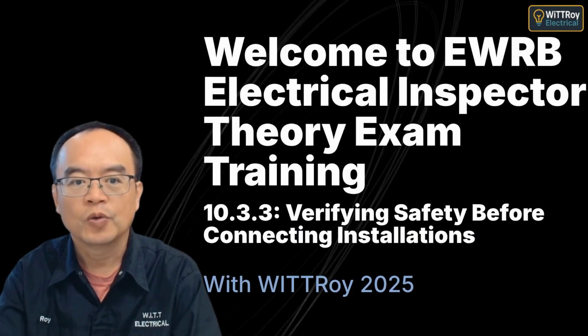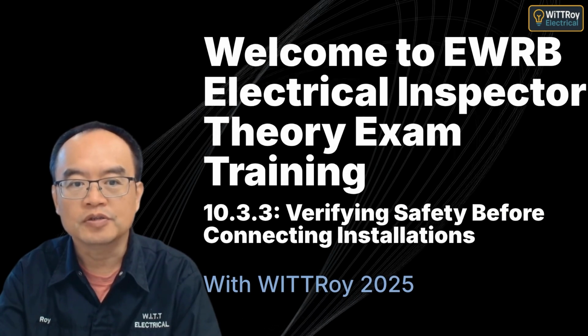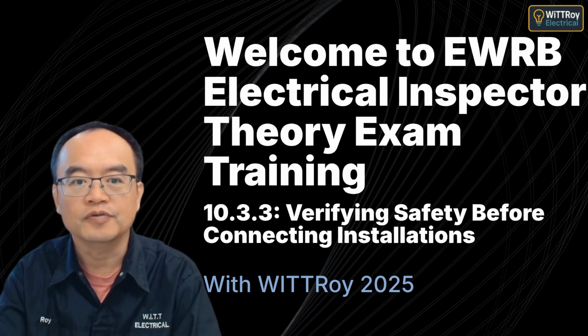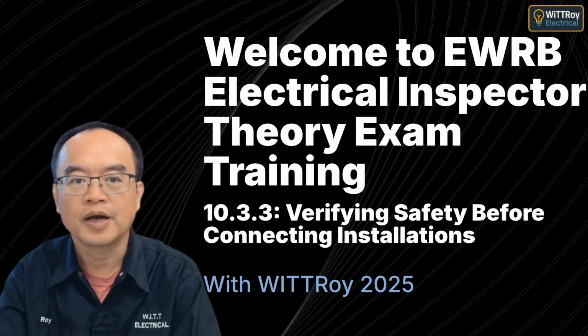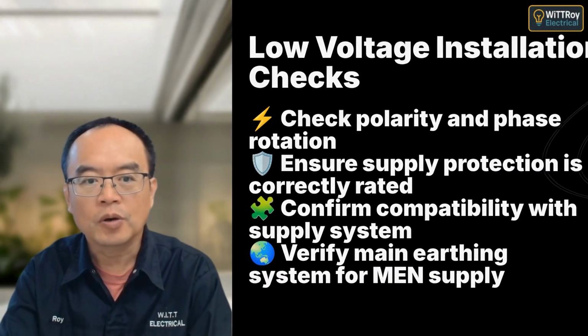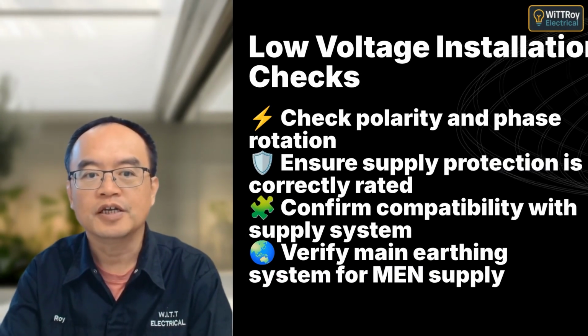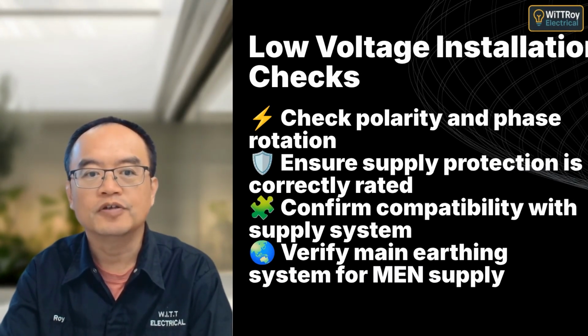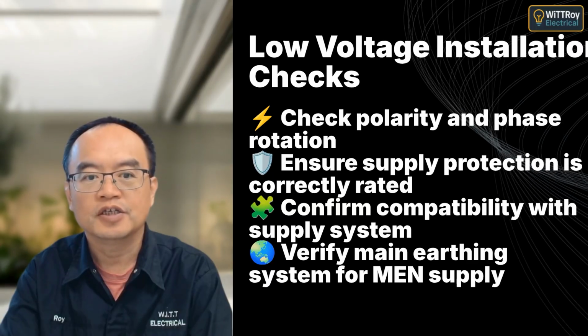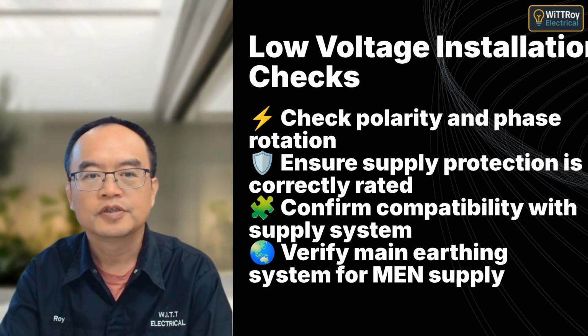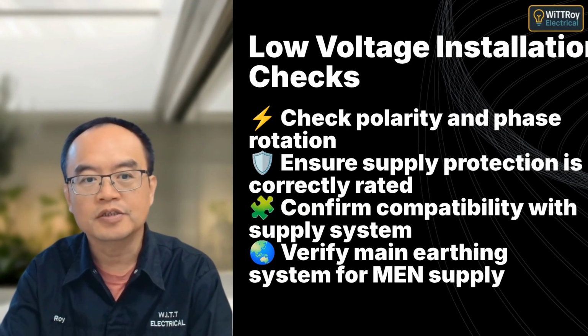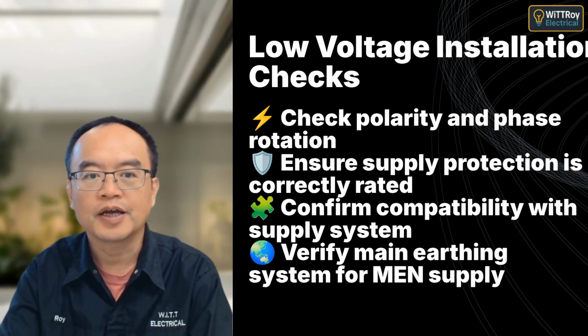Hi everyone, I'm Whitroy. Today we'll explore the critical steps needed to verify electrical safety before connecting installations to a power supply. Before connecting low voltage installations, check that polarity and phase rotation are correct, protection is rated correctly, the system is compatible, and for MEN supplies, confirm there is a main earthing system.